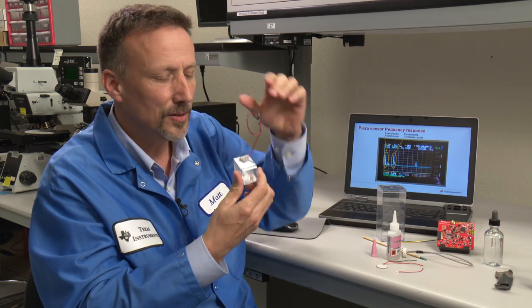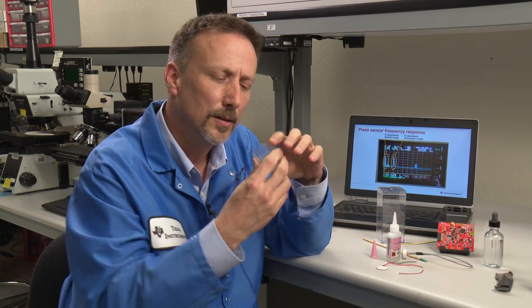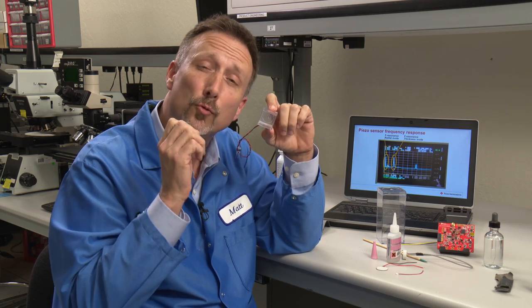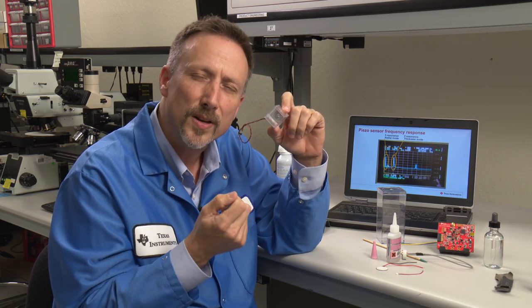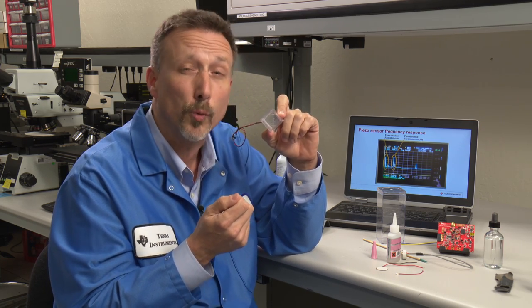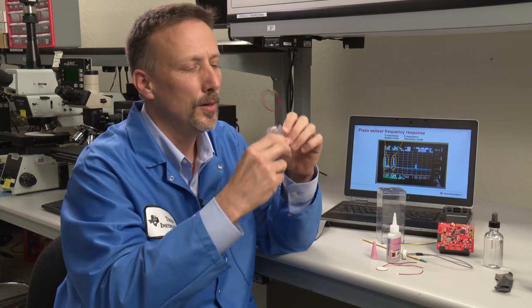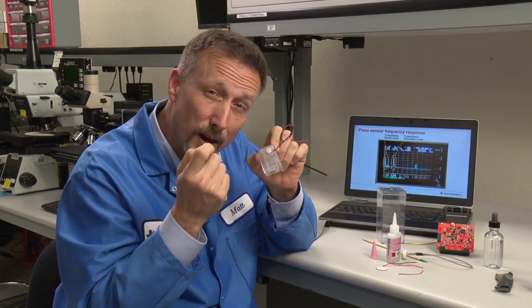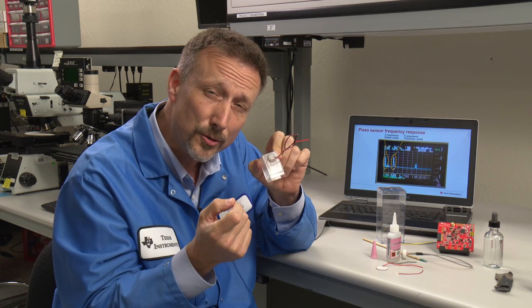In the case of trying to detect a signal very close to my transducer, every one of my transducers, when I excite it, they ring. This, in your transducer specification, is called ring down. By applying an absorptive adhesive to the back of the transducer, I can minimize that ring down.